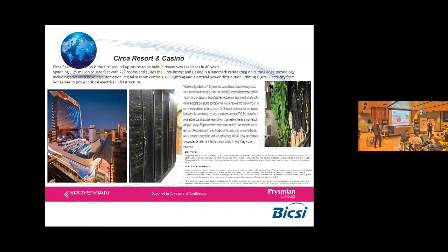But that VoltServer is actually powered by a UPS, so they could collapse the entire UPS system in the building. No longer did they need a UPS every floor or every second floor. They brought it all back down into a single UPS unit that delivers the power to the VoltServer, and then the VoltServer delivers the power to the receivers on the floors.